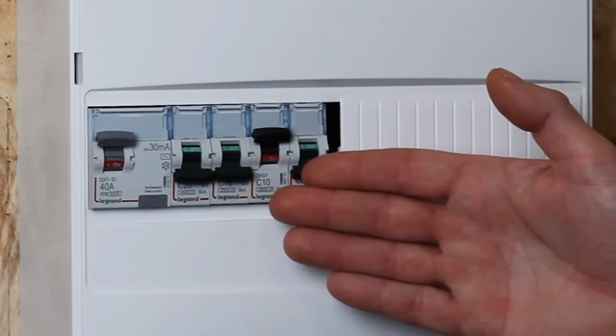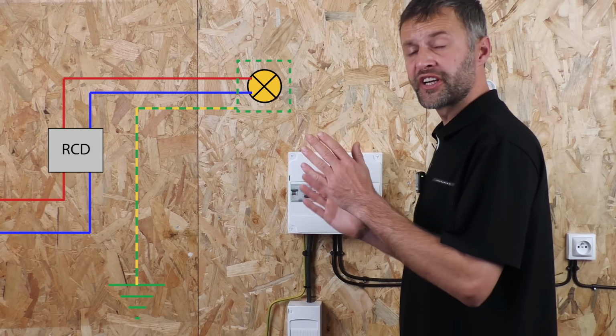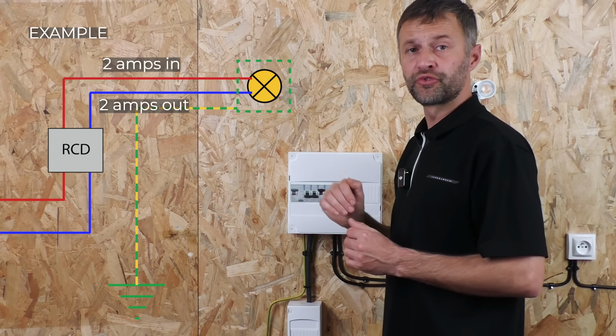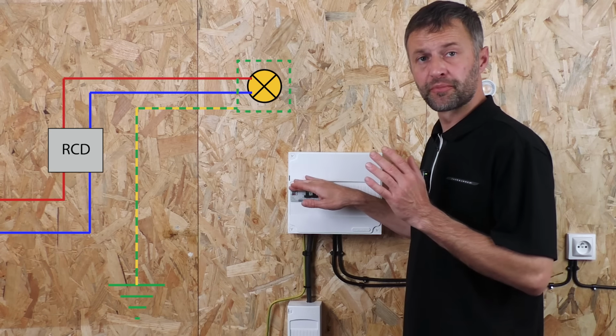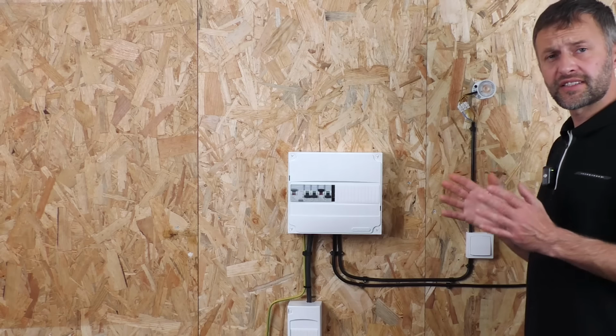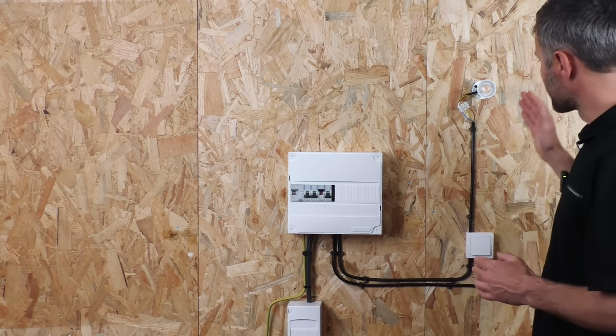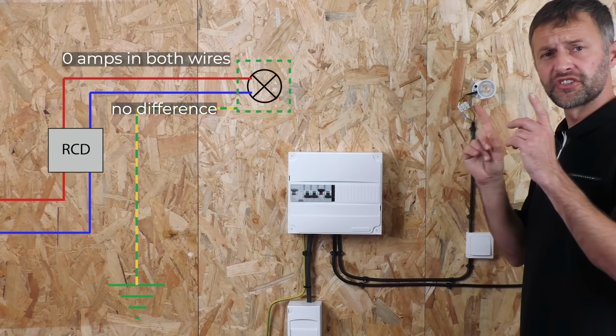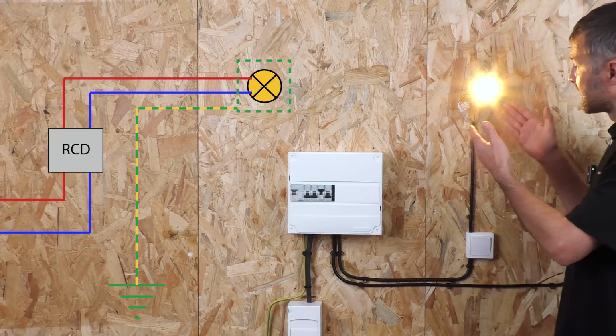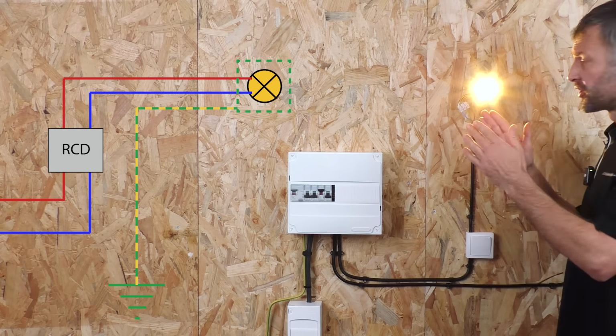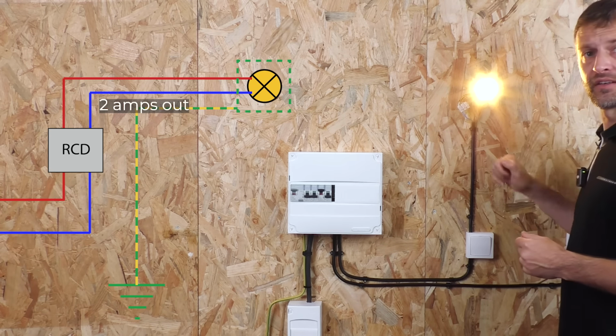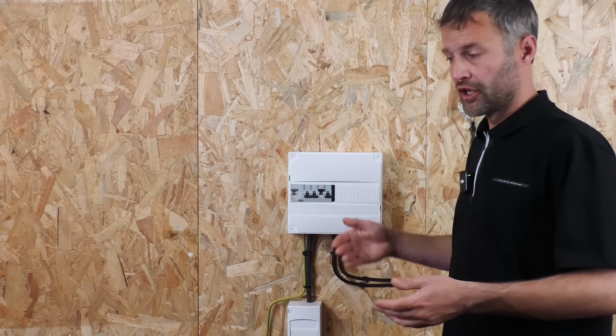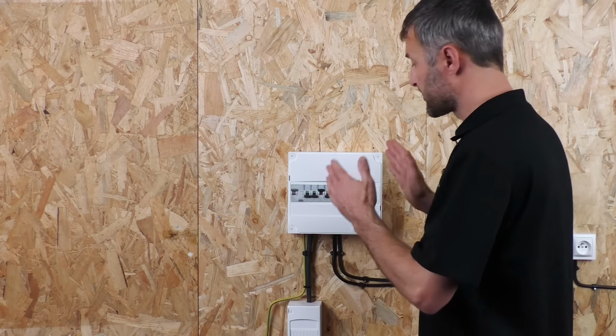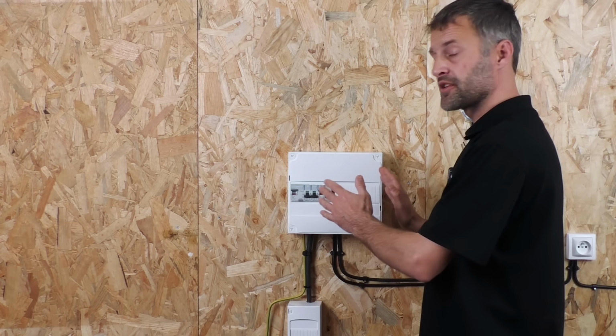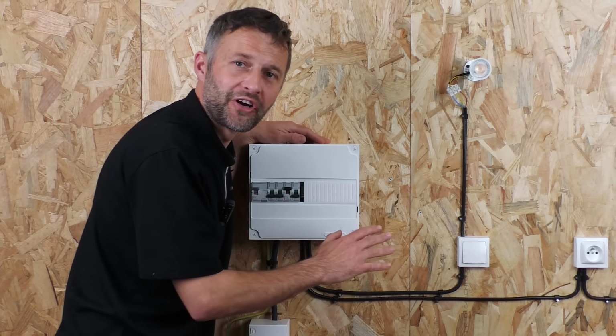Unlike a circuit breaker, an RCD constantly compares the current going out through live with the current returning back through neutral. If there's any difference, it trips. It doesn't matter if a device is connected or not, because if it's not connected, the current in both live and neutral is zero. And if it's connected, the current in both live and neutral should be equal, because what comes out must go back. So if a current starts leaking somewhere else, through an earth or through a person, an RCD quickly detects that imbalance and disconnects the power. And that's what keeps the system safe in the background.